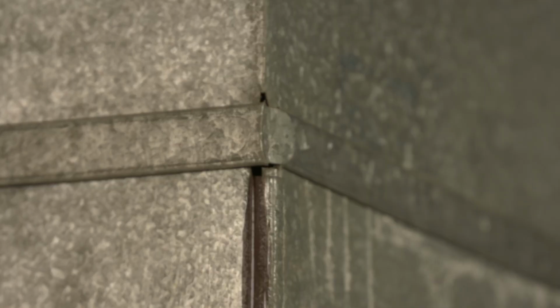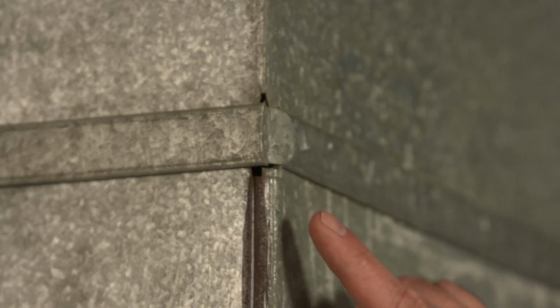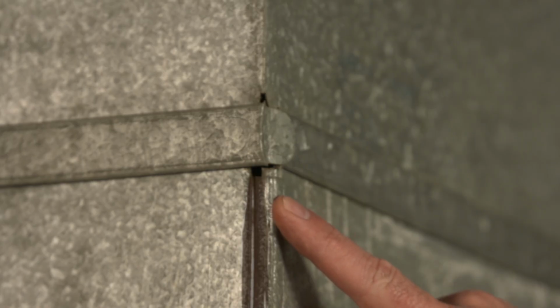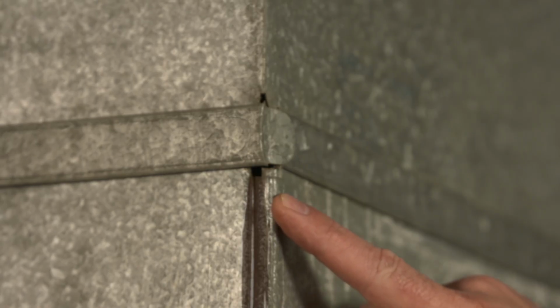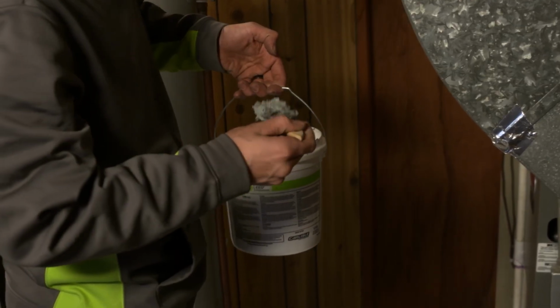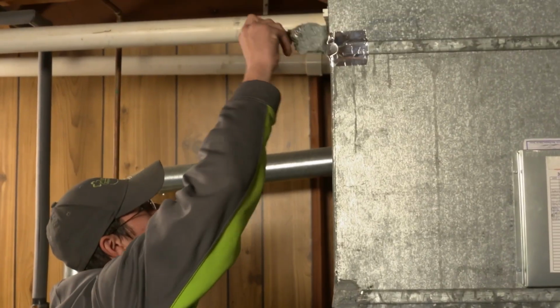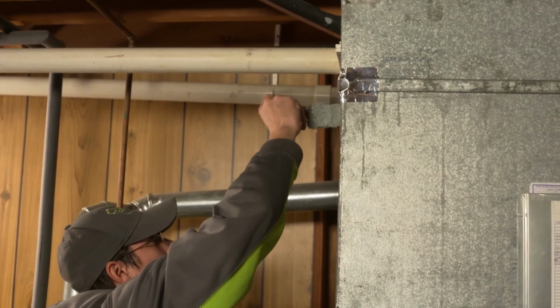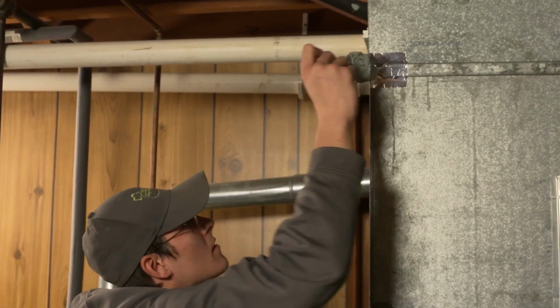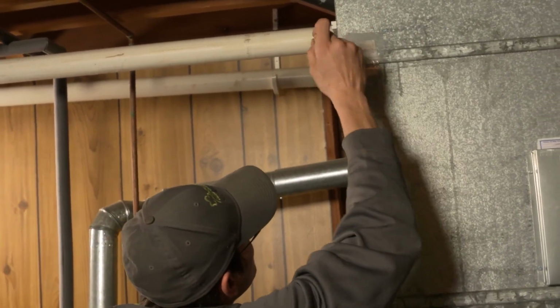Check your ductwork for leaks that could be robbing you of efficiency. These often show up as dirt streaks on the ductwork, especially near seams. Duct mastic can be applied to seal the leaks instead of duct tape, since tape can become less sticky and peel away, causing the leak to reappear.